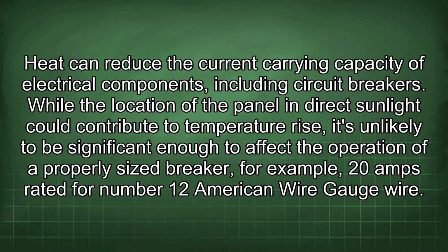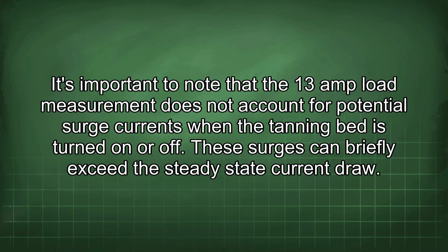Heat can reduce the current carrying capacity of electrical components, including circuit breakers. While the location of the panel in direct sunlight could contribute to temperature rise, it's unlikely to be significant enough to affect the operation of a properly sized breaker, for example, 20 amps rated for number 12 American wire gauge wire. It's important to note that the 13 amp load measurement does not account for potential surge currents when the tanning bed is turned on or off. These surges can briefly exceed the steady state current draw.